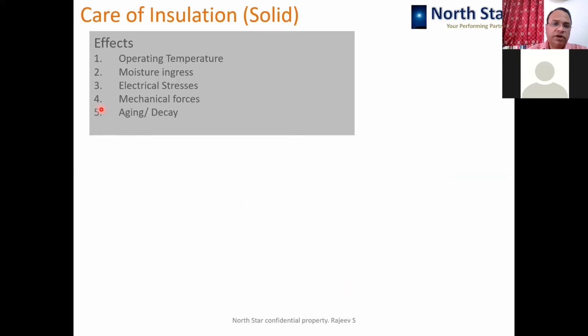So in case of solid insulation, it is getting affected because of operating temperature, moisture ingress, electrical stresses, mechanical forces, and aging decay. The pity with solid insulation is that whatever effect of usage is happening is not reversible, that is irreversible. It is the most important and critical point as far as transformer insulation is concerned.